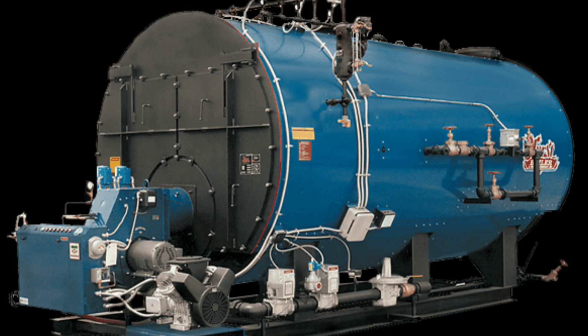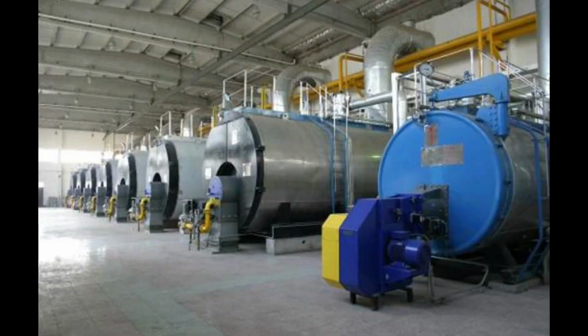So why is preservation necessary? To prevent corrosion of internal boiler surfaces, especially from oxygen and moisture, to avoid scaling or pitting inside boiler tubes and drums, to maintain the integrity and efficiency of the boiler for future use, and to reduce the risk of boiler failure, leakage, or unsafe startup.